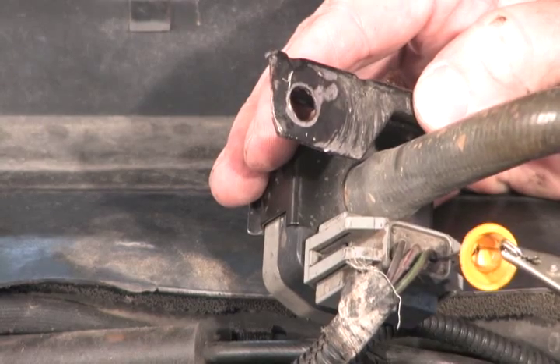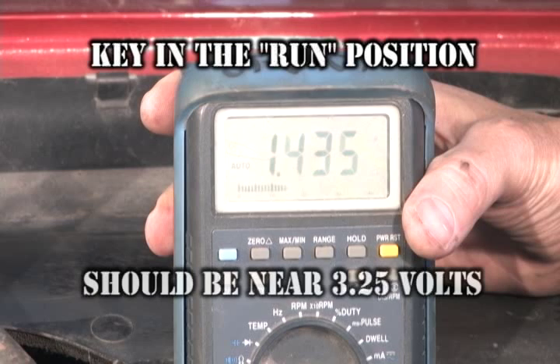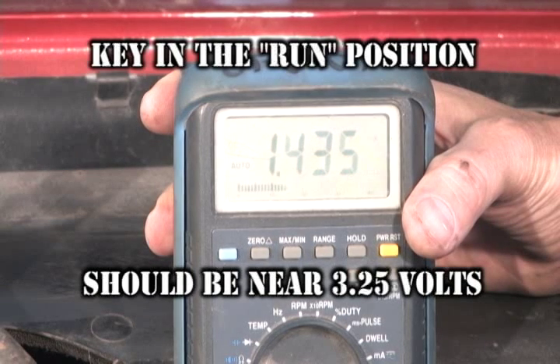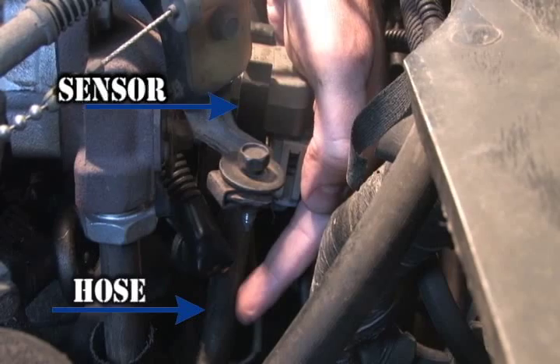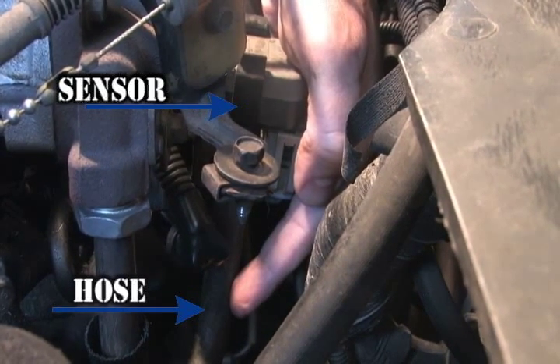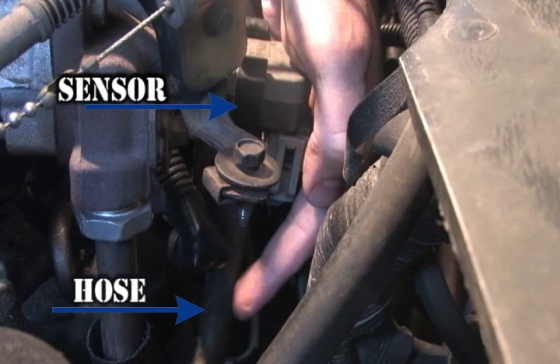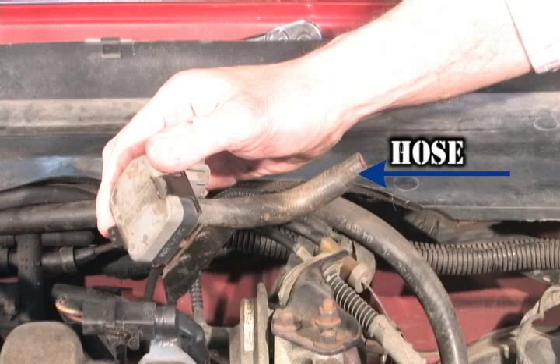The reading on your meter is 1.43 volts, well below the expected 3.25 volt specification. This sensor is faulty and needs replacement. Replacing the sensor requires us to remove the sensing hose from the sensor. Use care when removing this hose. Damaging it will require replacement with the application-specific hose.